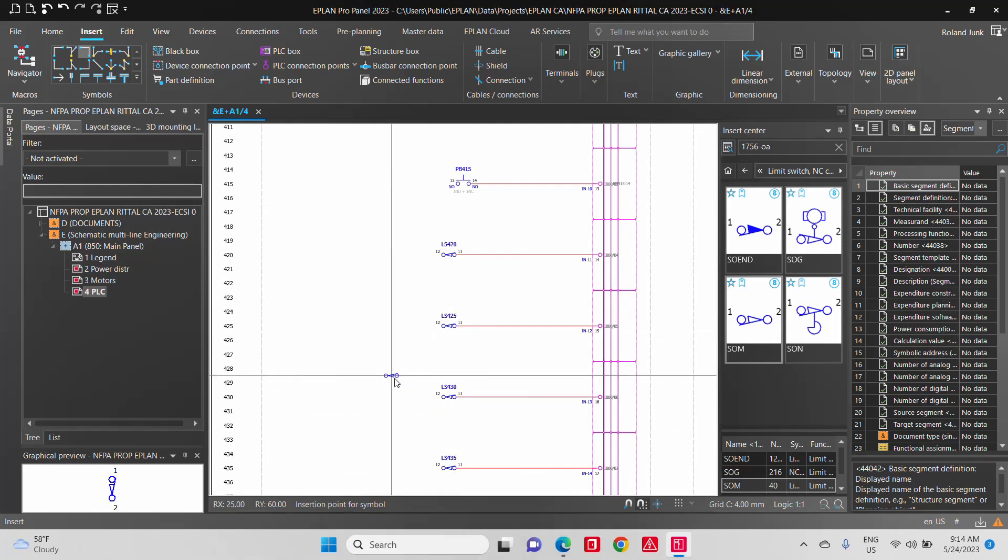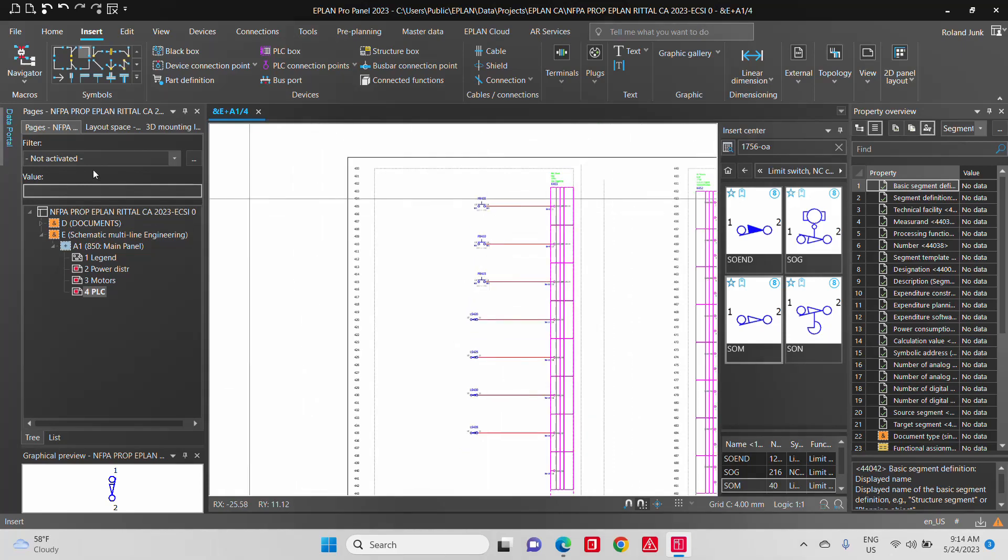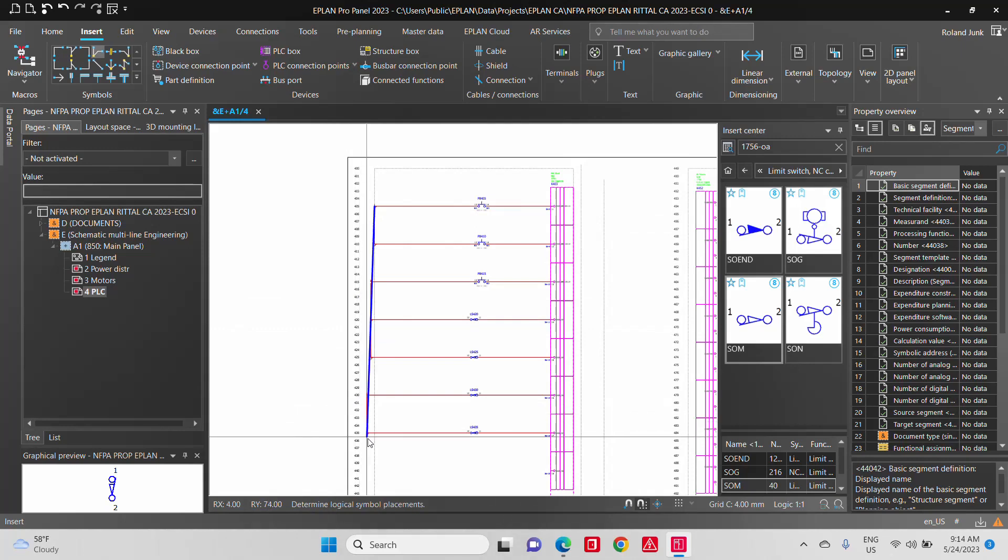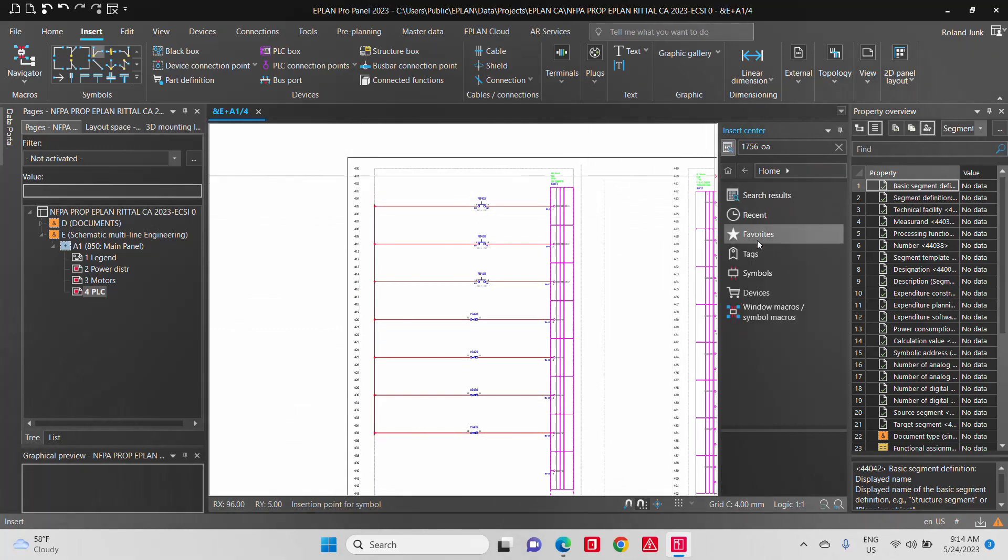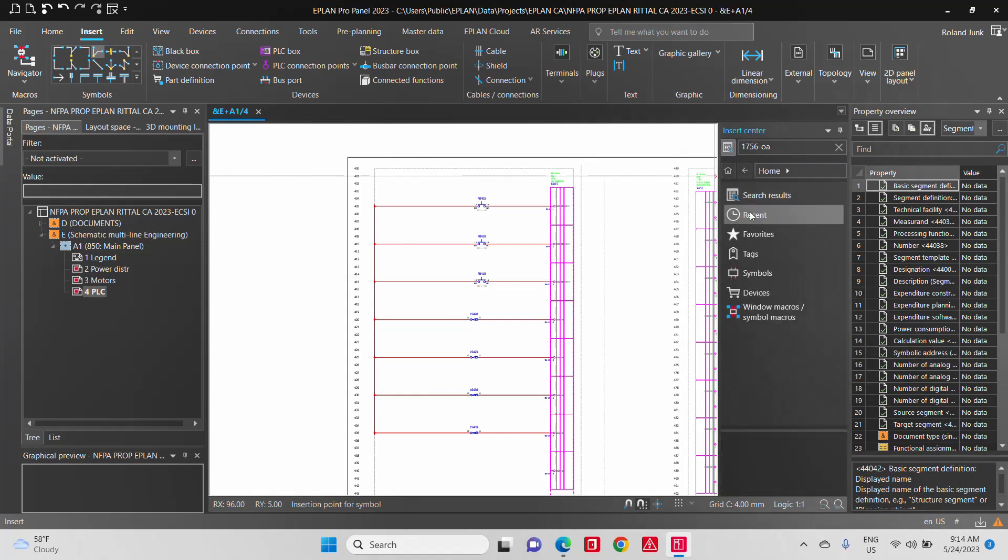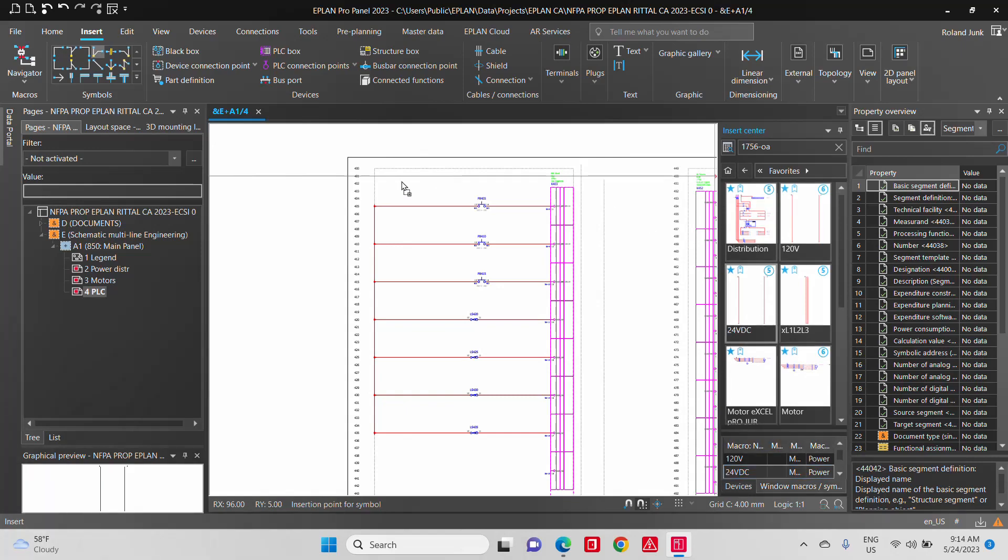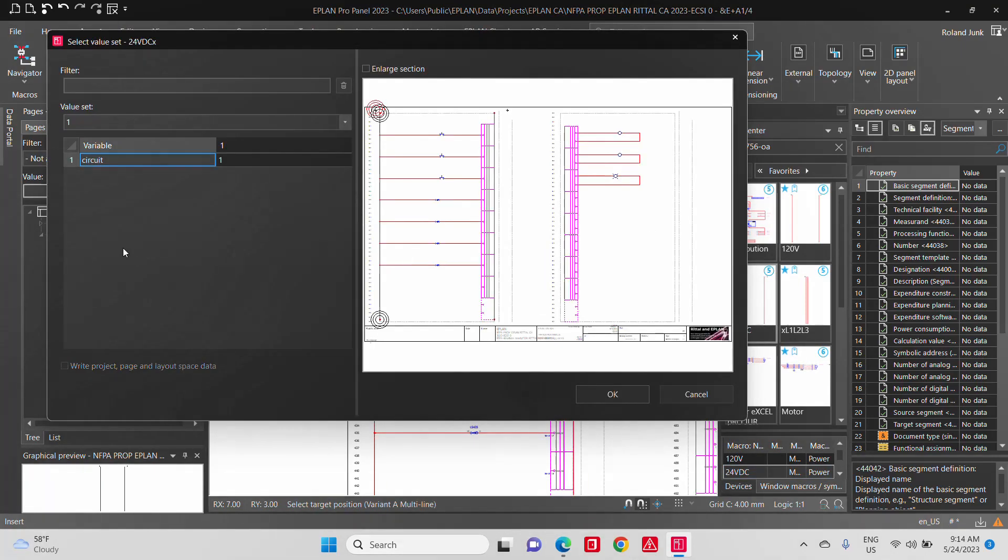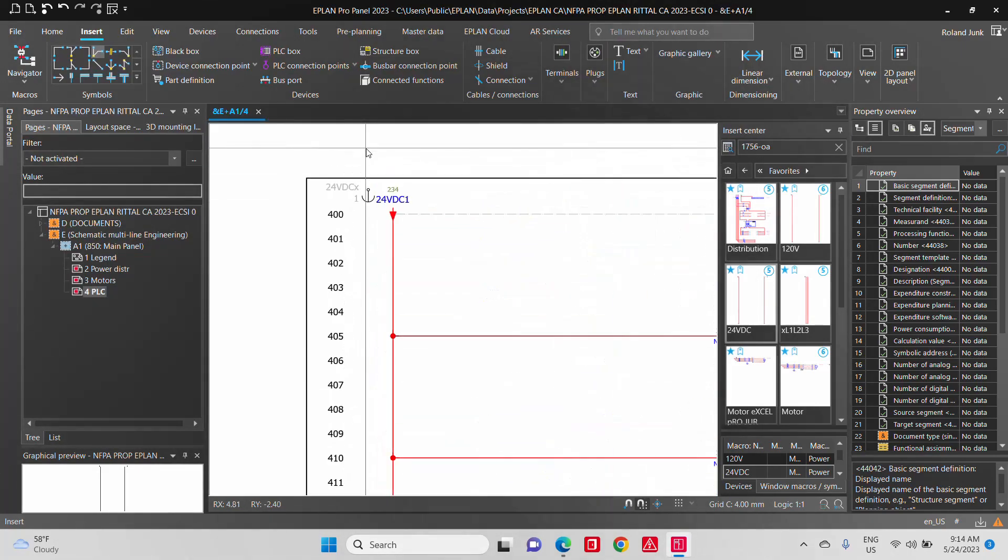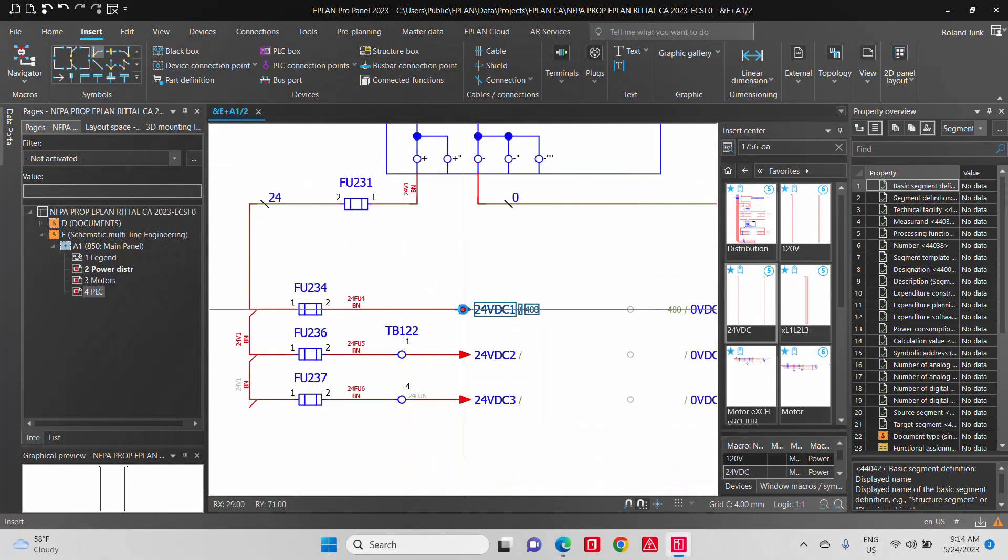So of course, these four pilot lights plus these push buttons here will have to be powered up with some 24 volts. So what I'm going to do here is I'm just going to put a line of 24 volts, which will be cross-referenced to a previous page that I have. So I can simply drag and drop a line of 24 volt like this, and it will connect in the cross-reference and the power will actually come from that previous page.